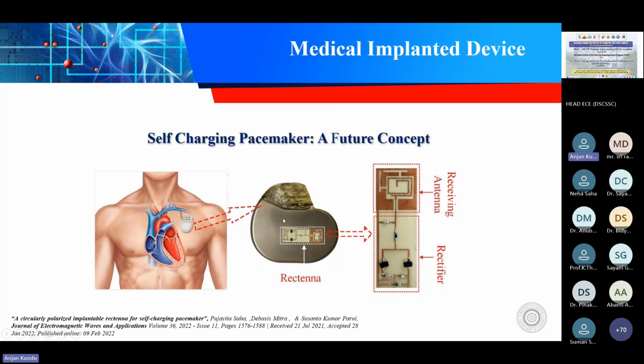In the pacemaker, almost 3/4 of this black portion contains a battery, which is not rechargeable till now. So whenever a patient is using a pacemaker, that patient has to be admitted at a regular interval of 5 to 7 years, the lifetime of that pacemaker. Again an OT will be done, and a new pacemaker has to be placed, replacing the old pacemaker, because the battery will die.